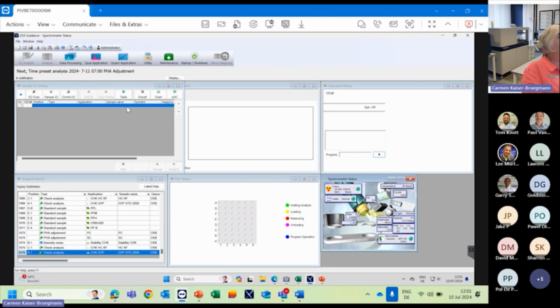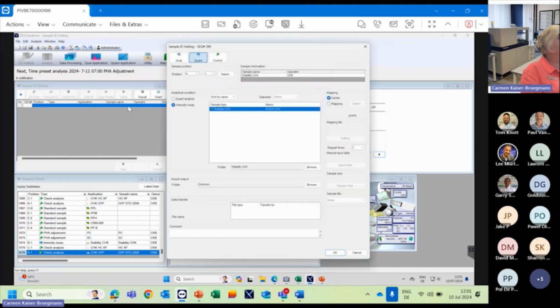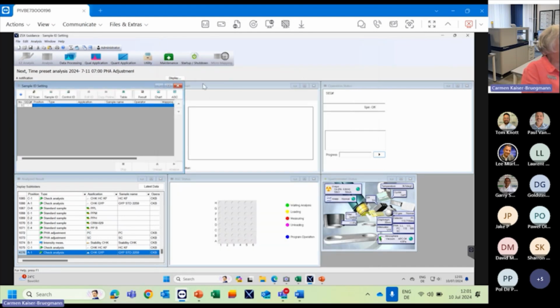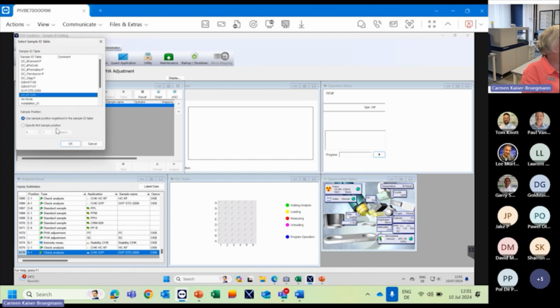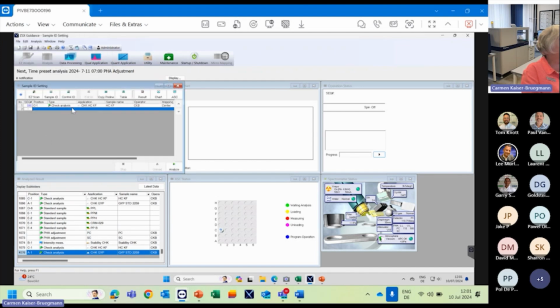So if you would like to create a measurement, you would double click on the blue line, and you can choose between the qualitative, which is semi-quantitative, or quantitative methods. And you also have a control. So this is where you would measure check samples, drift correction samples, or even measure your calibration standards. You can also create analytical tables. So, for example, I will now just create some measurements. So this is a check sample.